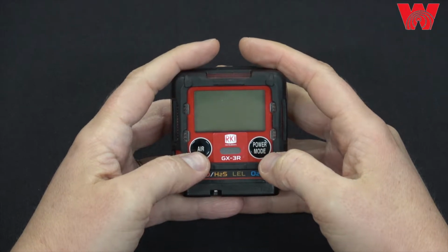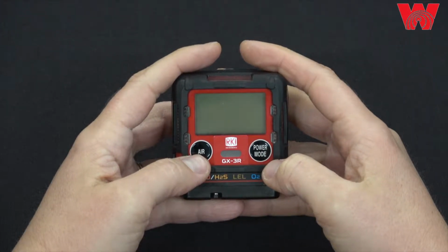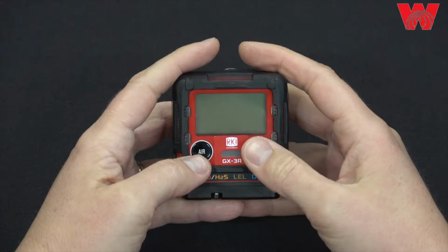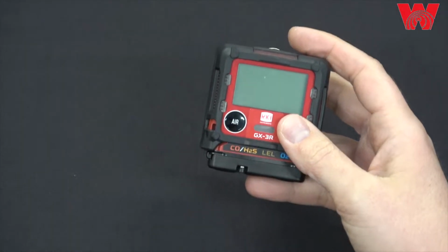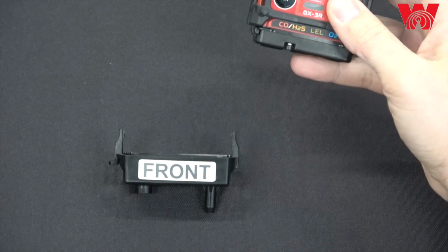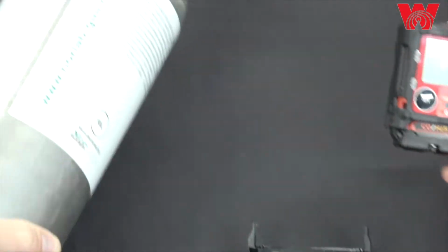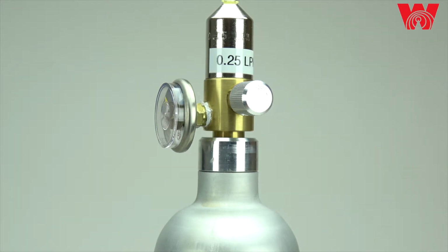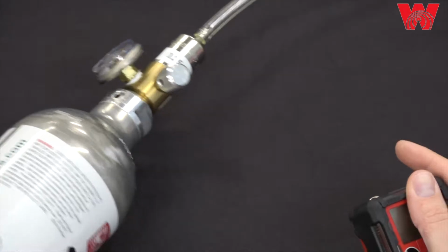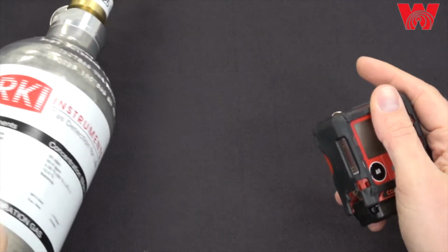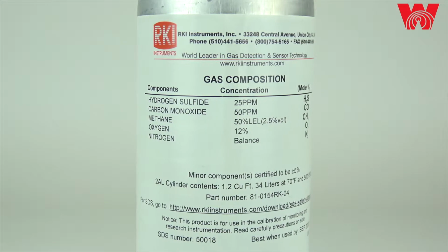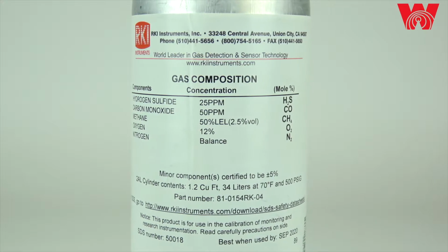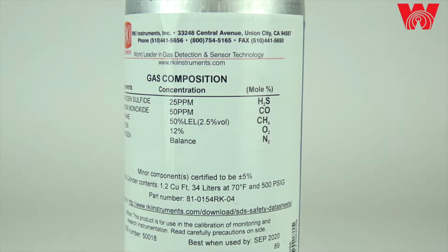Today I'm going to show you how to calibrate and bump test a GX3R. To do that, you need your GX3R, a calibration cup, a calibration cylinder with a 1/4 liter a minute regulator, and some calibration tubing. Your cylinder needs to have concentrations between 10% and 50% of the full-scale value of your channels.